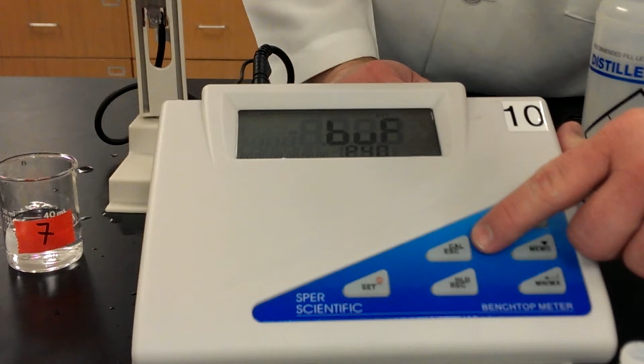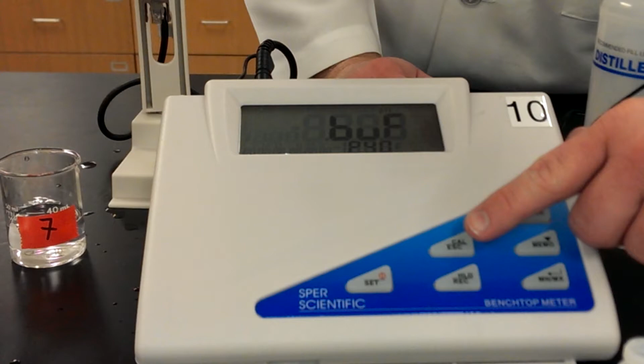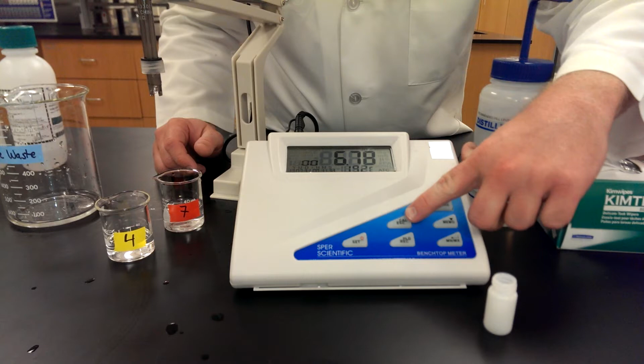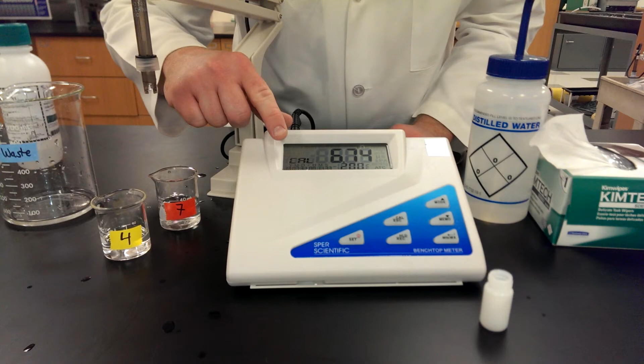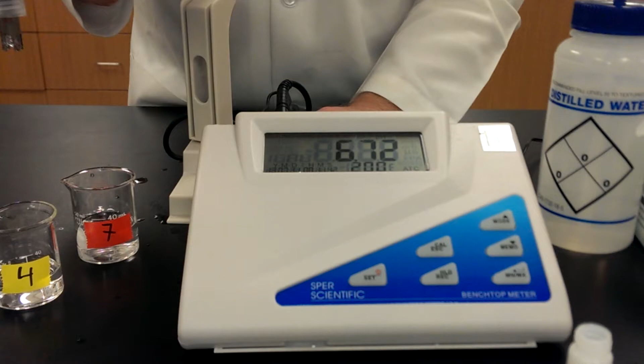Okay, so once we've done that, we can push the escape button. It says ESC on the bottom, a line above it, and then CAL. So we're just going to push that one time, and that's going to bring us back out to our main screen. Okay, so once we're at that point, it's time to start calibrating. We're going to push the same button again we just used to escape. That's also the calibrate button. So we're going to push that one time. You should see CAL flashing across your screen. That's now in calibrate mode.